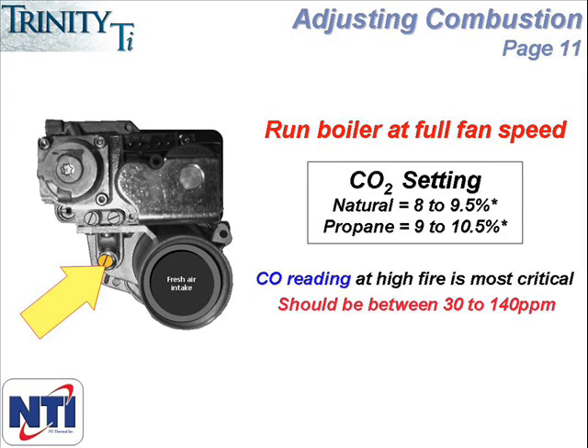If the CO number is over 140, then slowly reduce the amount of gas until the reading is below 140 or the CO2 is reduced to 8%. If the CO2 reading is below 8% and the CO is still above 140, you'll need to contact NTI for technical assistance.